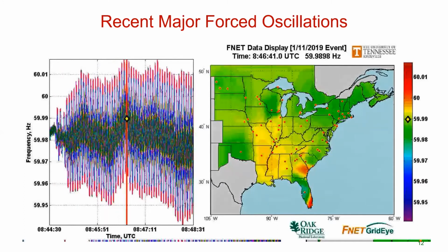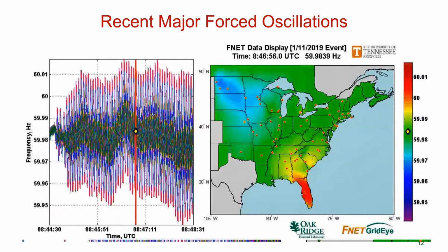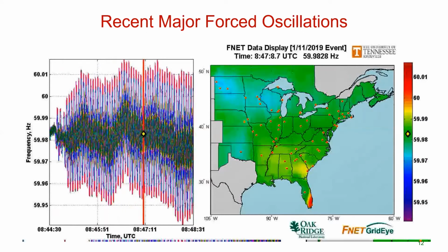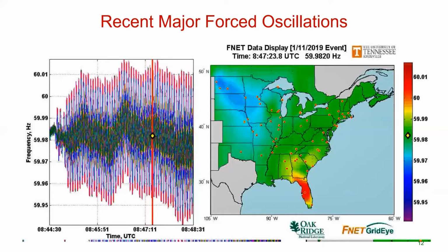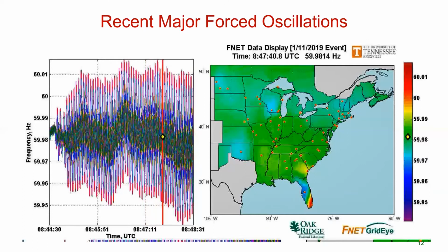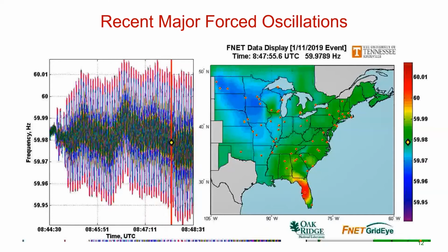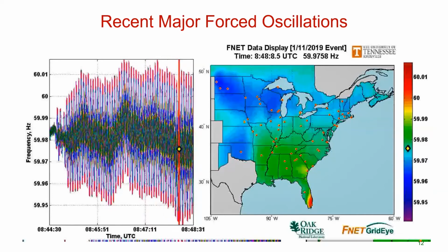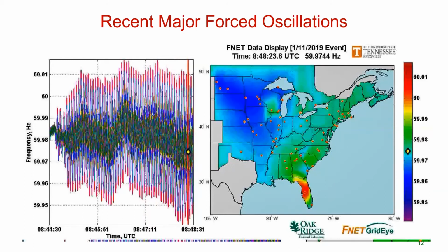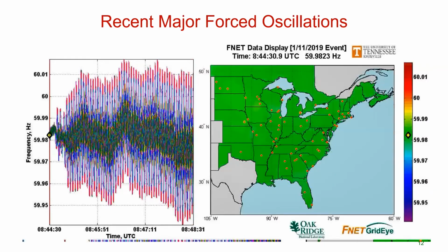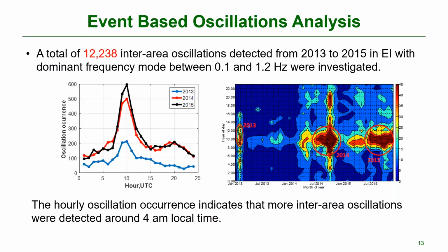But another type of oscillation we see a lot now is forced oscillation. So you have a malfunction in your system. Let's say your governor control is malfunctioning. In this case, this is all monitored, and this is out of our sensors. One of the generators in Florida actually had a sensor fail. When the sensor failed, the voltage was measured to be 0. So the system shut down. And then the control was designed so that when everything looks fine, they reclose and restart. So this continuous control motion set up a forced oscillation. And usually the source is very difficult to find. And they do happen quite a lot.